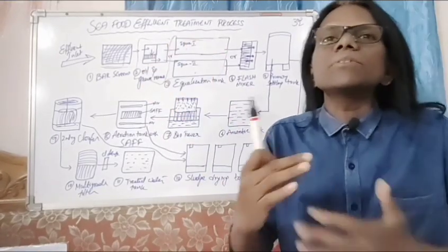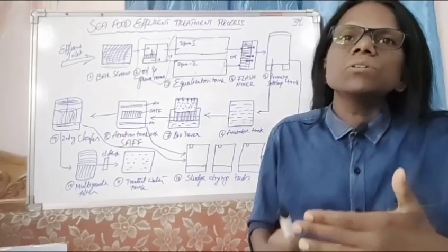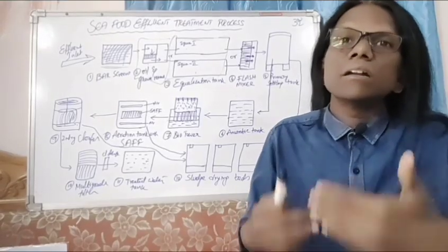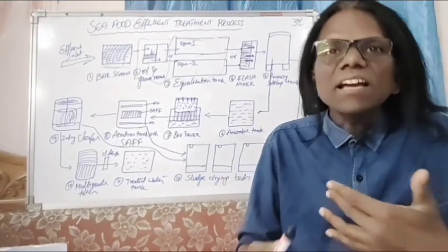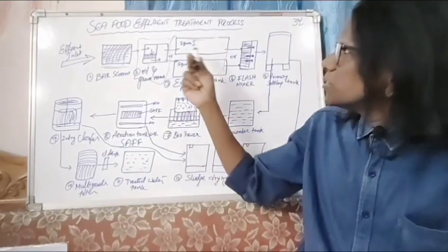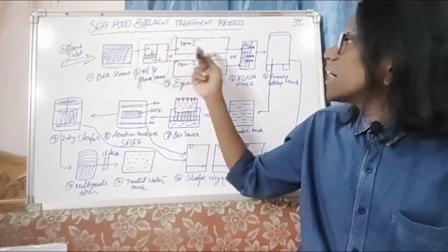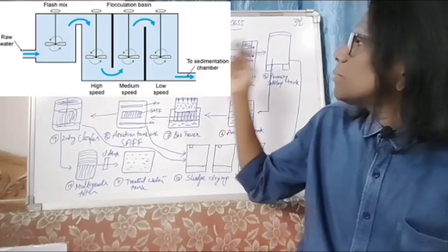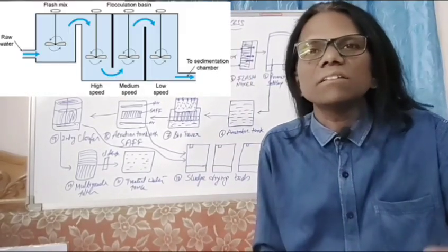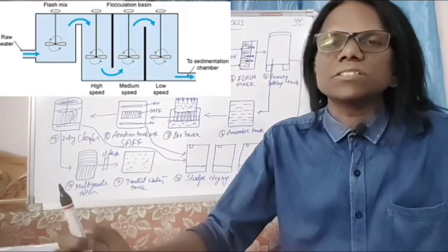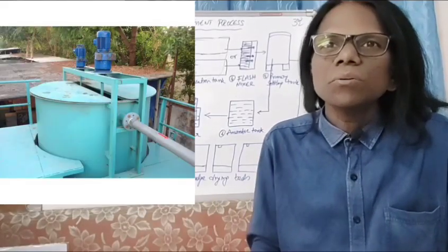In the meantime, we have to run the aeration continuously. We have to make sure the aeration runs continuously to neutralize the chlorine residuals. Once we make sure that the chlorine residues in the equalization tank are completely neutralized, we pass the water to the flocculation channel or flash mixer, where the chemical dosage also has to be added.